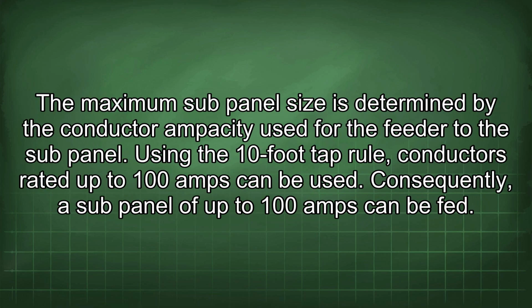The maximum sub-panel size is determined by the conductor ampacity used for the feeder to the sub-panel. Using the 10-foot tap rule, conductors rated up to 100 amps can be used. Consequently, a sub-panel of up to 100 amps can be fed.